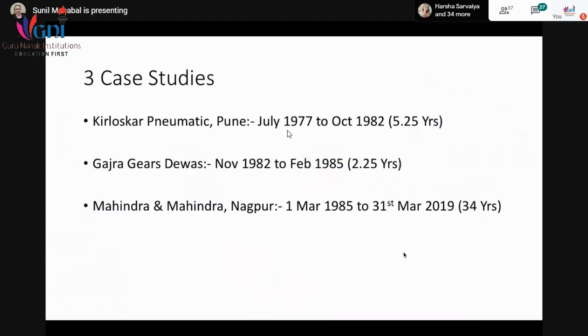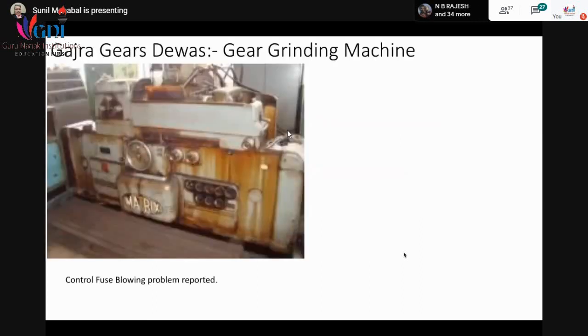Now the second one, which was at Gajra Gears, Dewas, which is in MP, Madhya Pradesh. It happened from November 1982 to February 1985. I worked there, and this particular problem was in a gear grinding machine. The company of that machine was Matrix, England. The problem reported by the operating side was a control fuse blowing problem. If you replace the fuse, the machine will start running and nothing will happen. Then sometime during the day or night, the fuse will blow again. So the maintenance crew was also in trouble: what is this problem which comes sometimes and doesn't appear at other times?